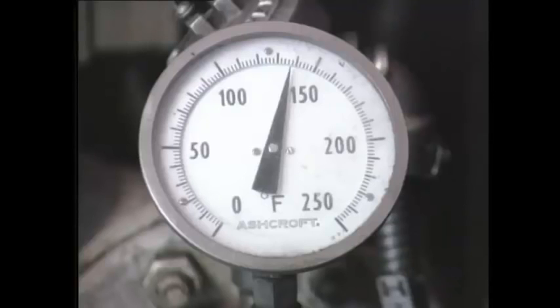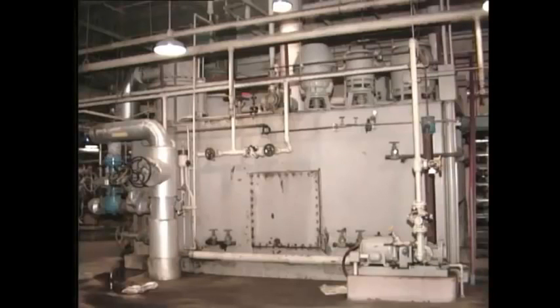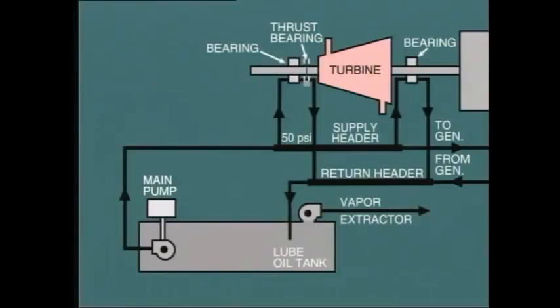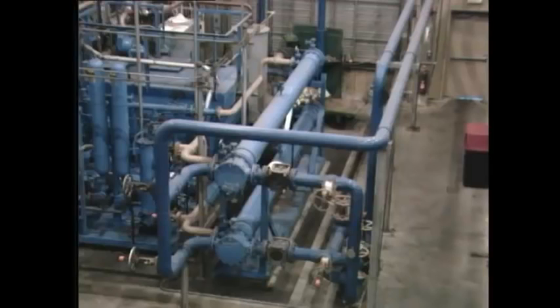As the lube oil passes through the bearings, it picks up heat and its temperature rises, conducting heat away from the bearings. The effect of this would be to continuously raise the temperature of the oil in the tank. In order to prevent this, a cooler is provided, and this is usually placed in the path of the lube oil supply. The lube oil cooler is usually of the tube and shell type, with cooling water passing through the inside of the tubes. It is normal to fit two coolers so that one may be taken out of service for cleaning at any time. Thus, the change can be accomplished without interrupting the supply of oil.